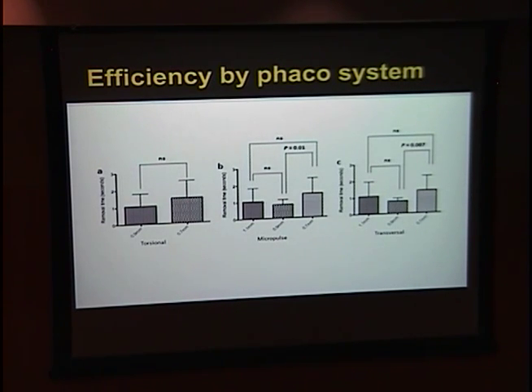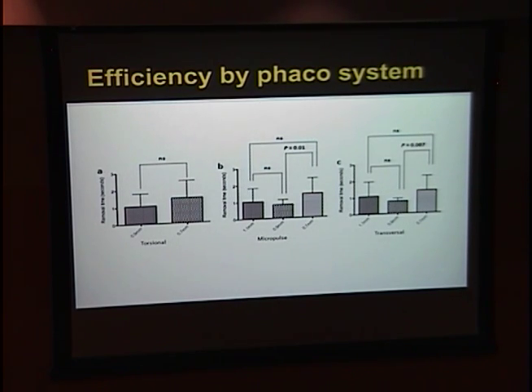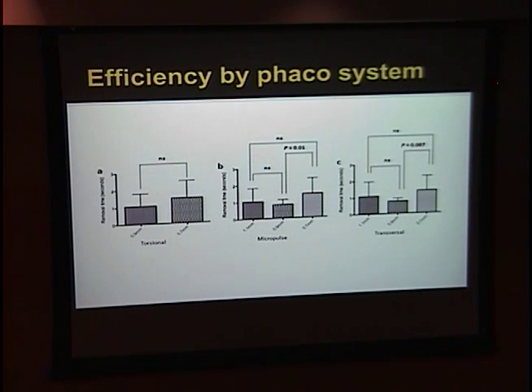These results suggested that the 0.7 mm tips were inefficient, likely because the small tip size resulted in less vacuum hold, suggesting the lens fragment cannot engage at the tip edge appropriately for removal. Similarly, for the 1.1 mm tips, efficiency was not the greatest because the tip size may have been too large for the nuclear fragment, not creating maximum vacuum hold and therefore insufficient vacuum to remove the fragment.